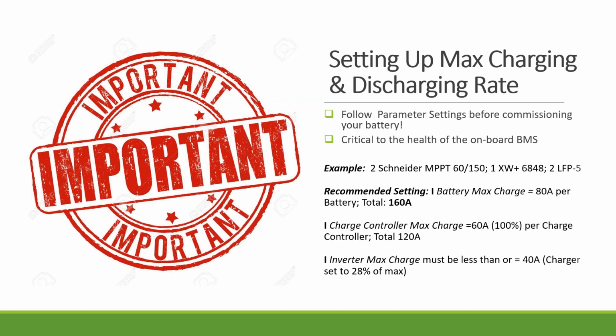We already touched on this, but I want to emphasize: if you use the inverter's data, you can flexibly group the charge controller and inverter together. Make sure you set up the inverter and charge controller's charging rate properly. The rule is usually to let the charge controller run at full capacity to take advantage of the solar, and on the inverter side, set the charging rate lower. That way you can still use the charge controller to charge the battery without harming it.